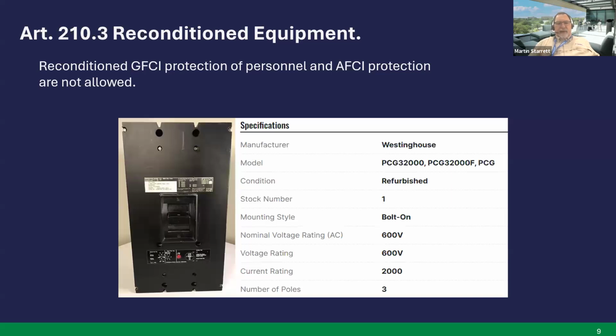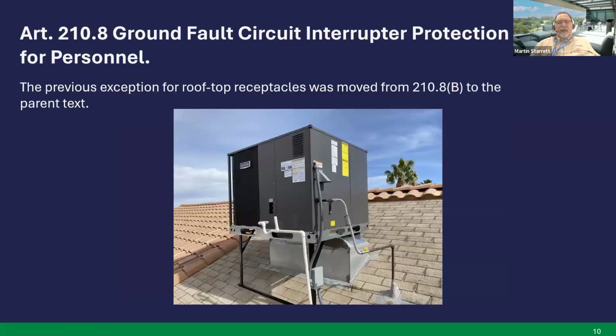So, as I said last session on Monday, that dot three is where you'll find your reconditioned equipment requirements. And we have that in Article 210. It tells you that reconditioned GFCI protection of personnel and AFCI protection are not allowed. So you will not be able to use any refurbished equipment for those items. Next slide. All right, Article 210.8, ground fault circuit interrupter protection for personnel.